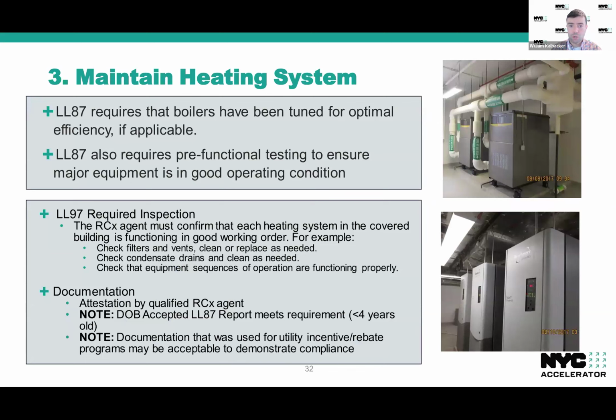Specifically, 87 requires that boilers are tuned for optimal efficiency where applicable. And it also requires certain pre-functional testing to be done on major equipment to ensure that everything is in good operating condition. For 97 specifically, the RCX agent needs to confirm that all heating system components in the covered building are in good working order.